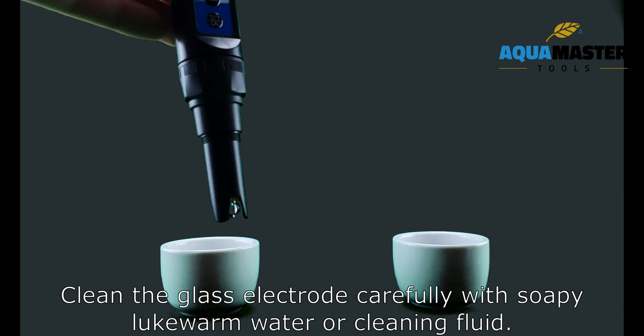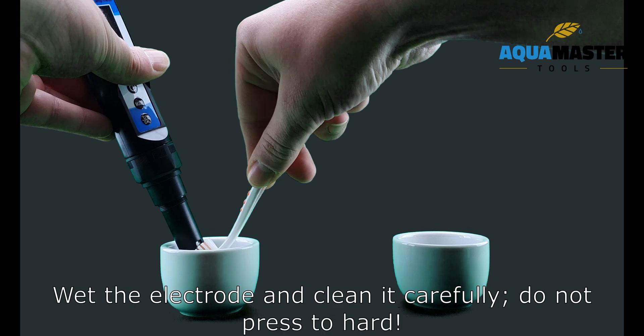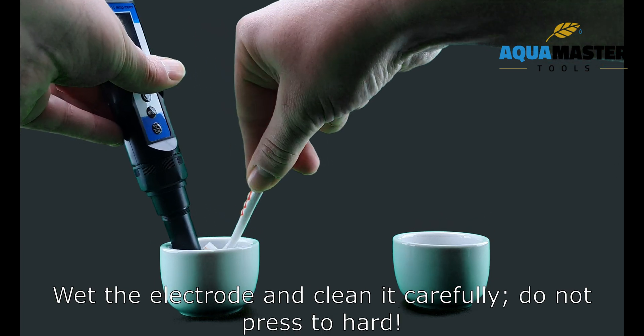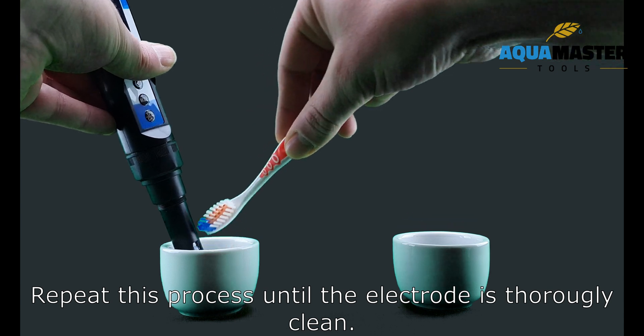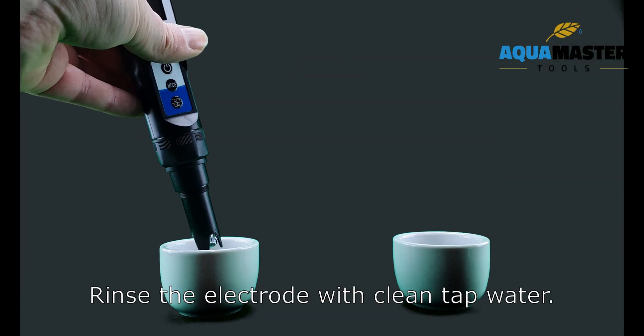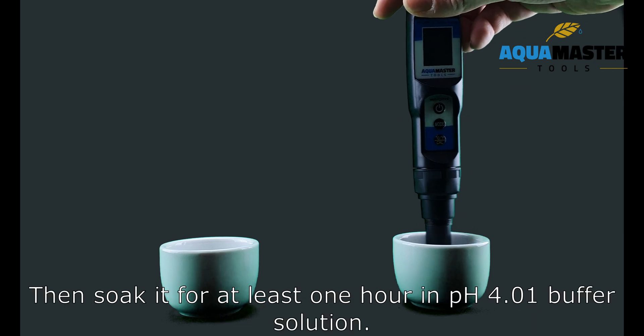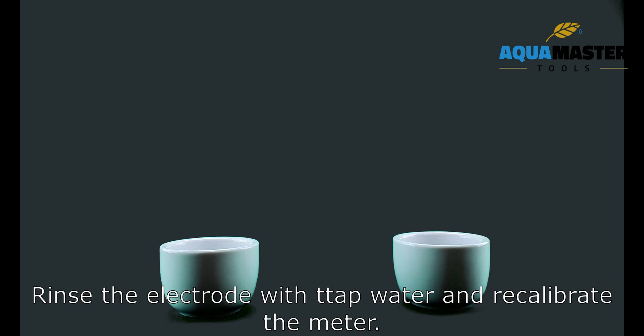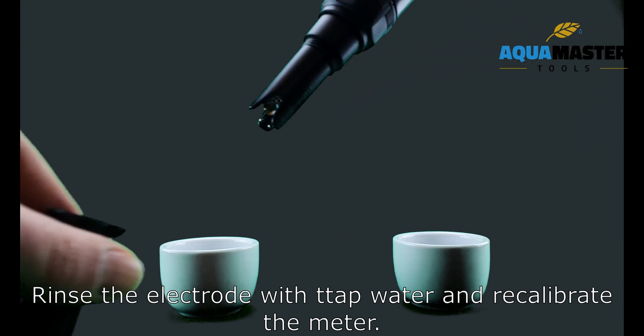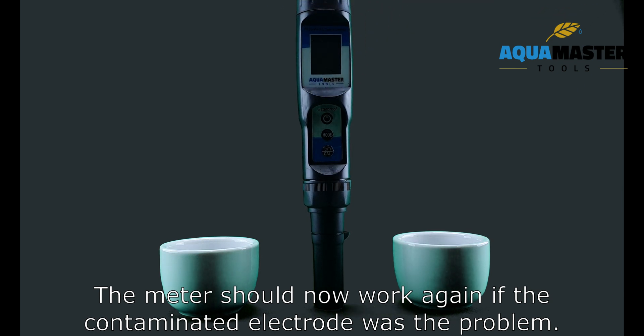Clean the glass electrode carefully with soapy water or cleaning fluid. Use a soft brush, wet the electrode, and clean it carefully — do not press too hard. Repeat this process until the electrode is thoroughly clean. Rinse with clean tap water, then soak it for at least one hour in pH 4.01 buffer solution. Rinse again with tap water and recalibrate the meter. The meter should now work again if the contaminated electrode was the problem.